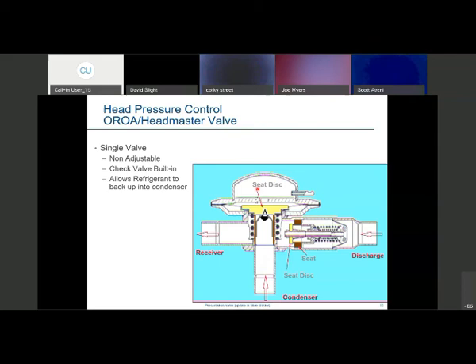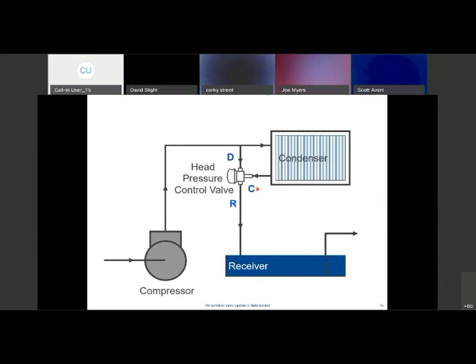Here's how it's piped in: condenser effluent comes into the bottom of the OROA valve, and there's a bypass line feeding into the receiver. As the condenser-side pressure starts to fall, it closes off and feeds a little bit of discharge gas through to the receiver to maintain that pressure, backing up and flooding the condenser. Again, the receiver has to be large enough to cover the volume of the condenser.